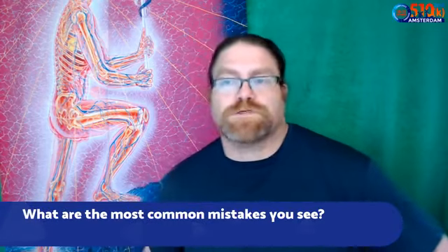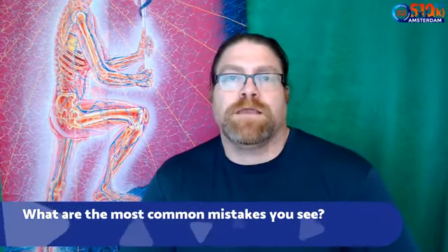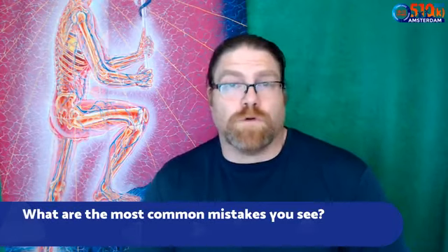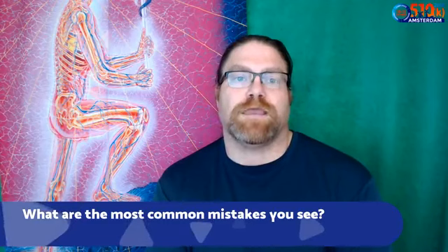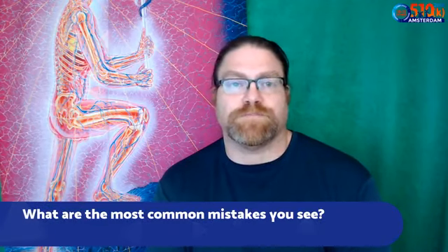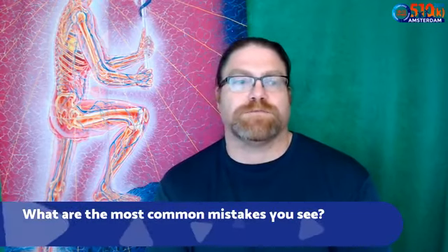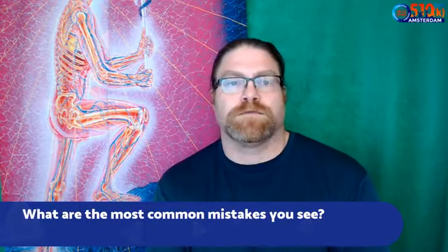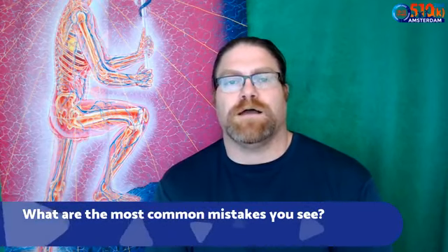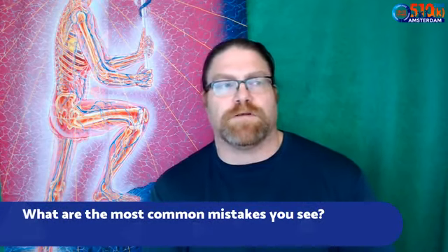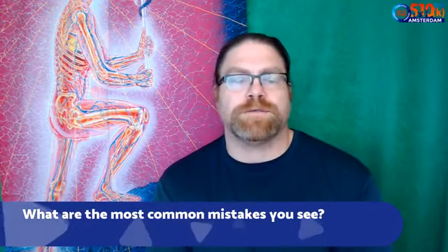So what are some of the most common mistakes that I see when companies submit labeling? Often it's the prescription use only legend that I see missing. A lot of times they have forgotten and left things in other languages and haven't made it clear. Sometimes I see other mistakes, things that aren't allowed in the US market. They make claims that they're making in Europe, but they're not allowed to make in the US. So those are some of the most common mistakes.